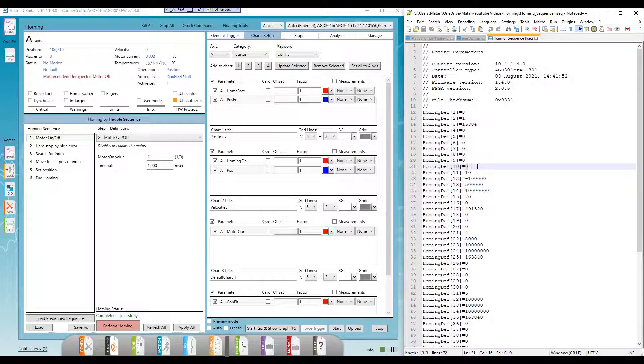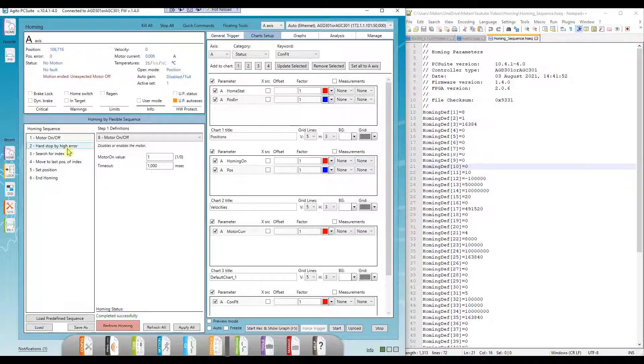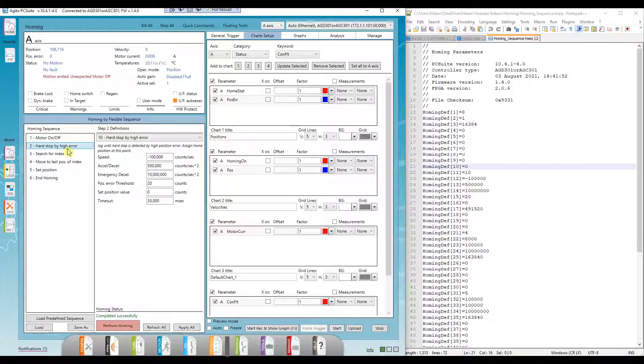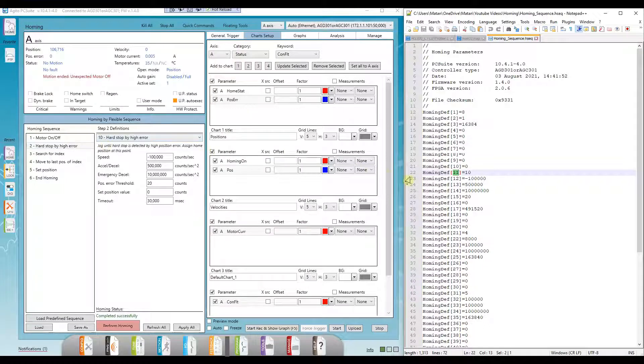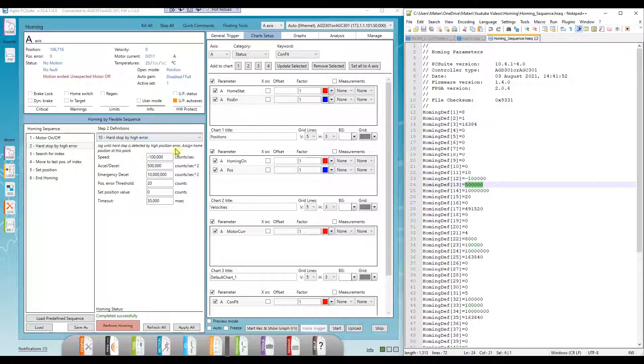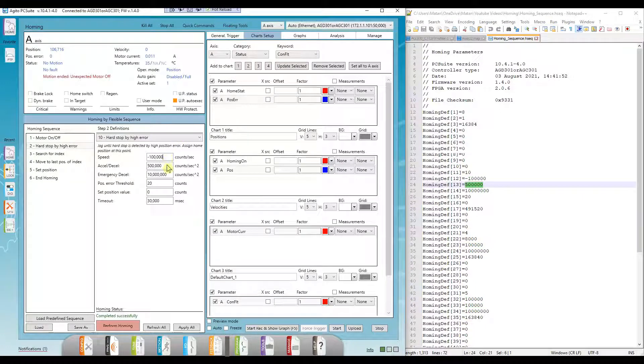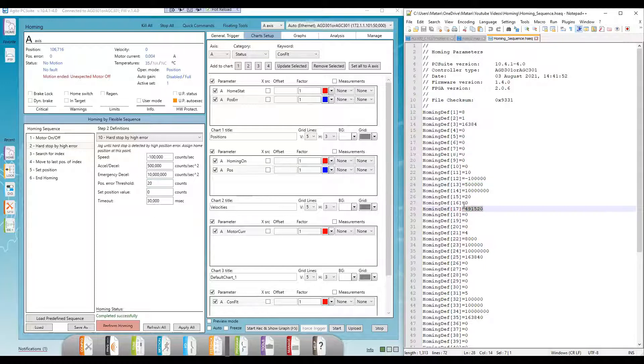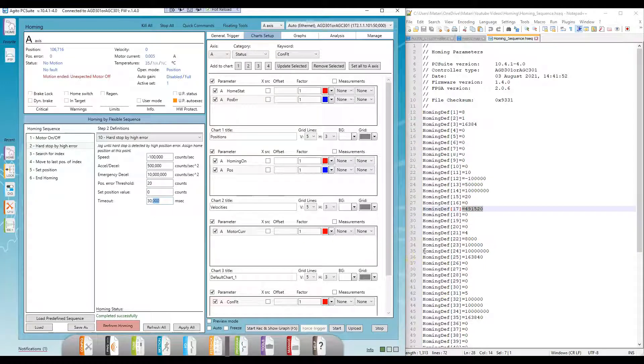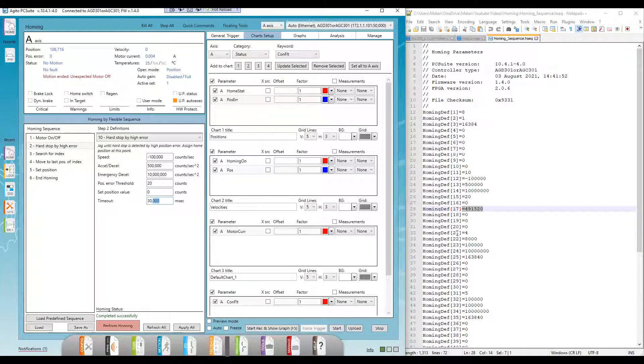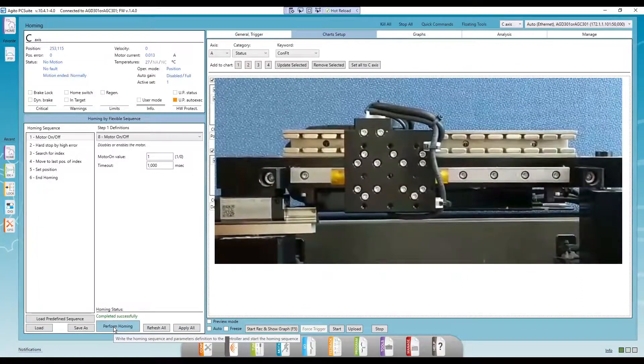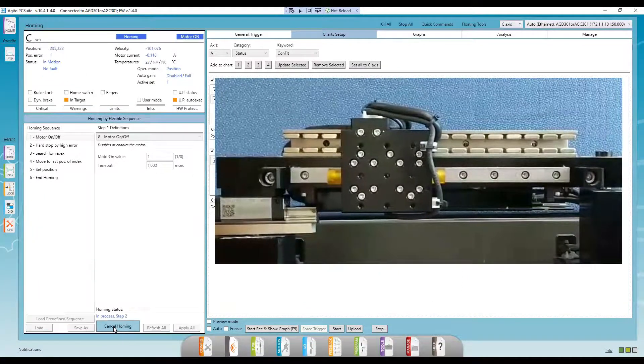The next step starts at index number 11. The hard stop by high error step type is number 10. And we can see the following parameters filled out the same way as we set them in PCSuite. And again, the timeout value is in units of controller samples. The next steps start from indices 21, 31, 41, and so on. Alright, let's see it in action. First, from the homing window interface.